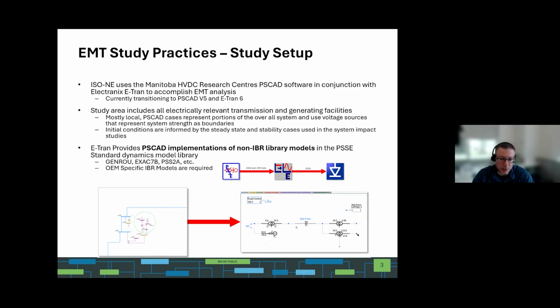We use Manitoba HVDC's PSCAD software in conjunction with Electranix's E-Tran software to do this. We'll start with a PSSE case, which is positive sequence modeling, and convert that into an EMT case or PSCAD case, because we already have a lot of infrastructure set up around building models and cases in positive sequence space, so it doesn't make sense to re-accomplish that effort in EMT space. So we do port that over.